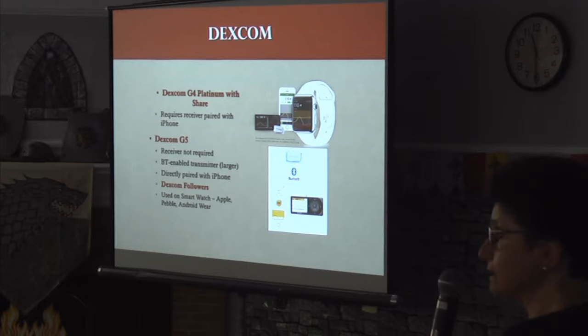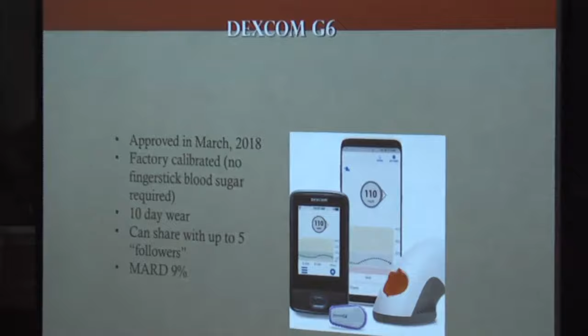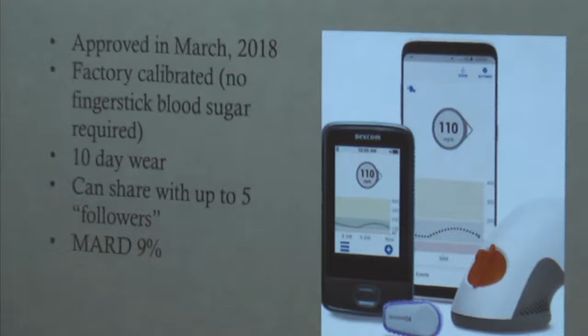So the G5 is approved for 7 days, and G6 is approved for 10 days. G5, I think I have G6 picture too. So G5 requires 2 calibrations per day, and this is the G6. So G6 does not need to be calibrated. It's factory calibrated, and it's a 10-day wear. And up to 5 people can follow you.